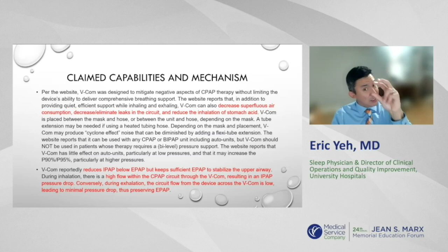So VCOM reportedly reduces IPAP below EPAP, but keeps sufficient EPAP to stabilize the upper airway. During inhalation, there is a high flow within the CPAP circuit through the VCOM, resulting in an IPAP pressure drop. Conversely, during exhalation, the circuit flow from the device across VCOM is low, leading to minimal pressure drops. As you see those 4 holes there, it's basically like a one-way valve out. But there are probably 2 of them. I'm not 100% sure, but two of them is a 2-way valve.